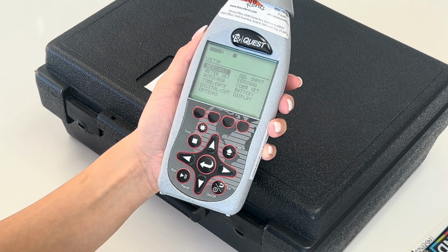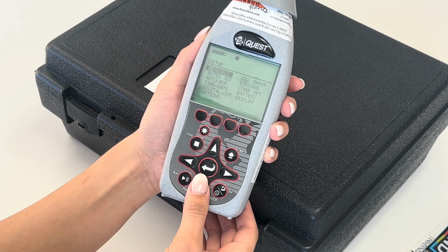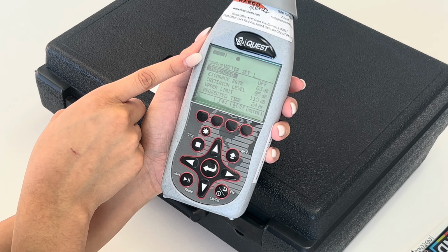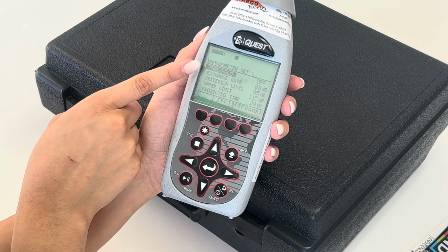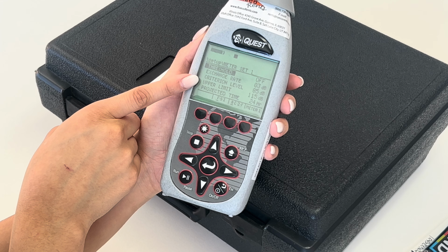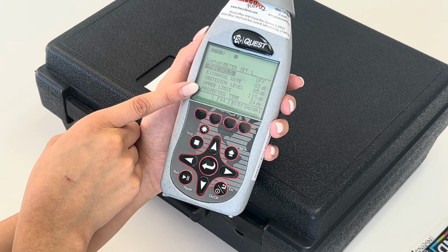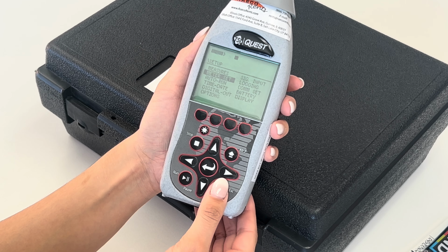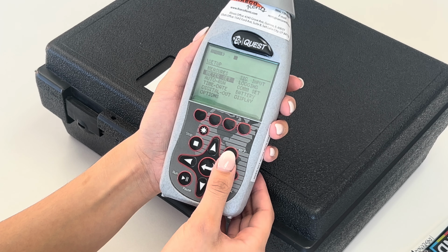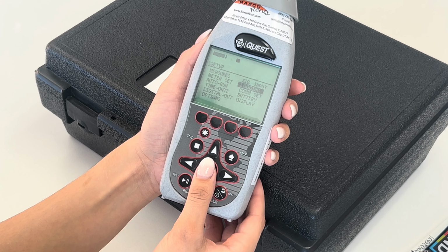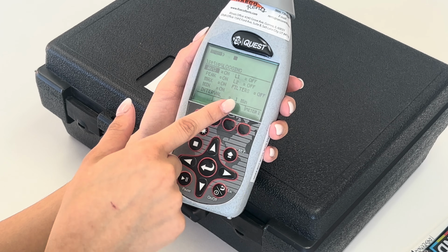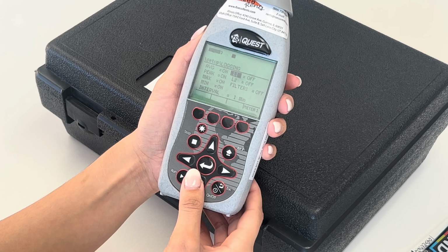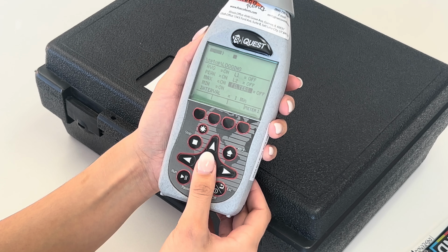In the setup menu, you can adjust the settings so that they are better suited for your project. If we go into meter setup, you can change the threshold, exchange rate, criterion level, upper limit, and projected time. To go back to the previous setup screen, press the back button. Due to our standard setup, we normally turn off the Octave Band filters. By going into the logging setting, you can turn the filters back on.